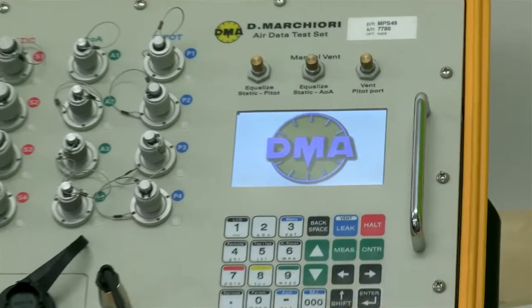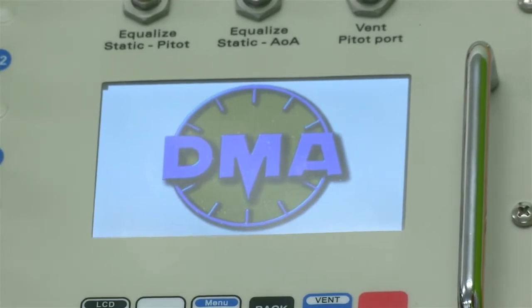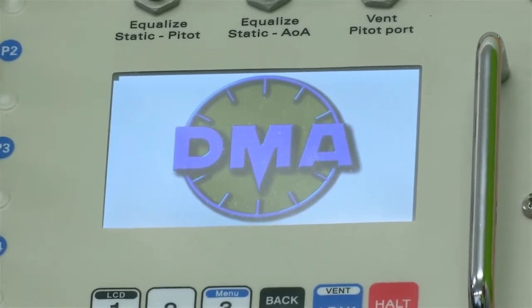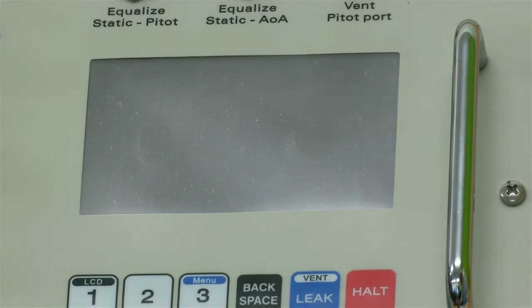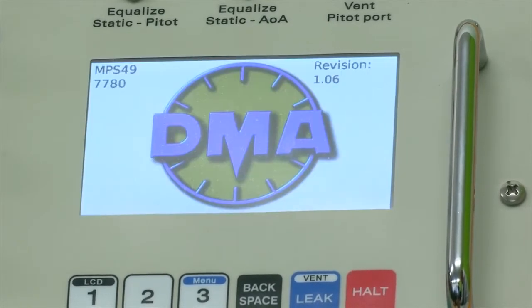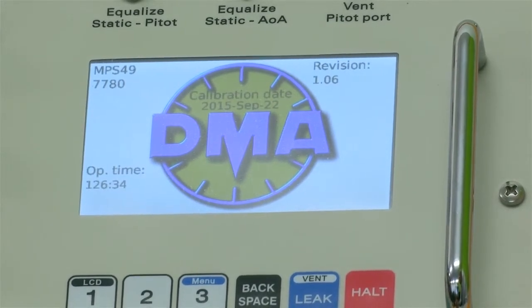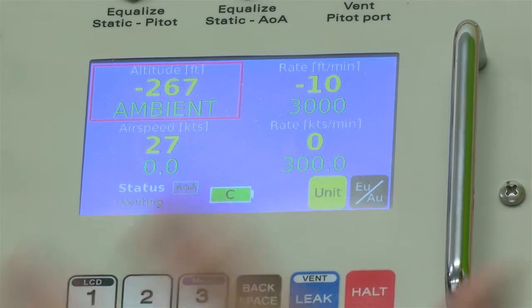We'll show how many running hours there have been for the internal pumps, and then we'll go through a startup procedure in terms of taking the instrument down to safe ambient values before we start. Well, we almost do. We have three different startup procedures. One, it will come straight online if we have a situation where we're very close to ambient. Fine.